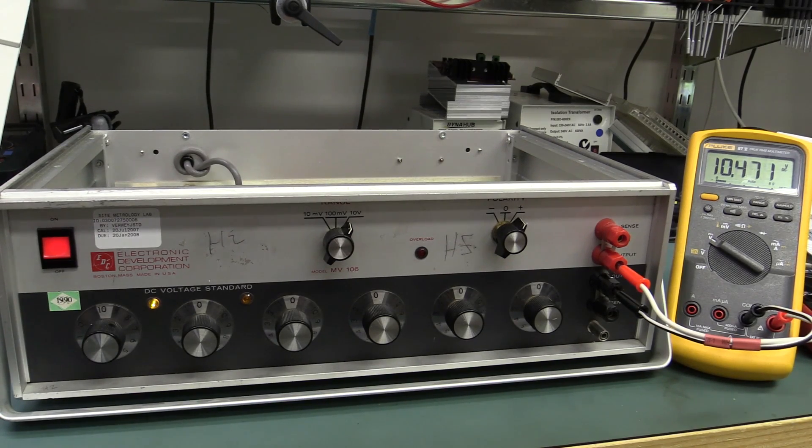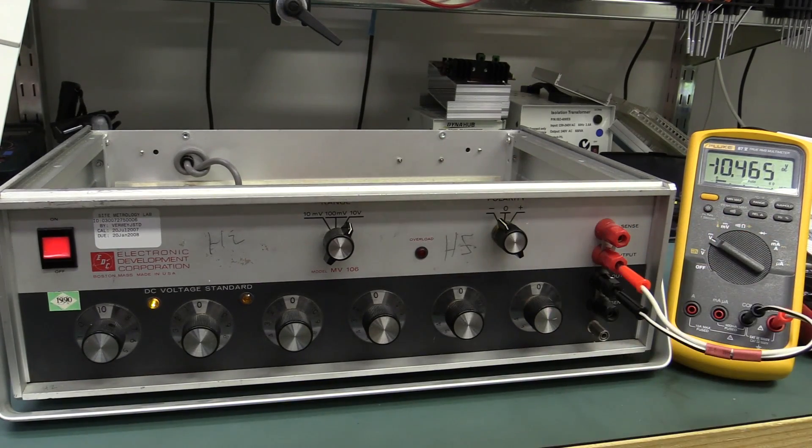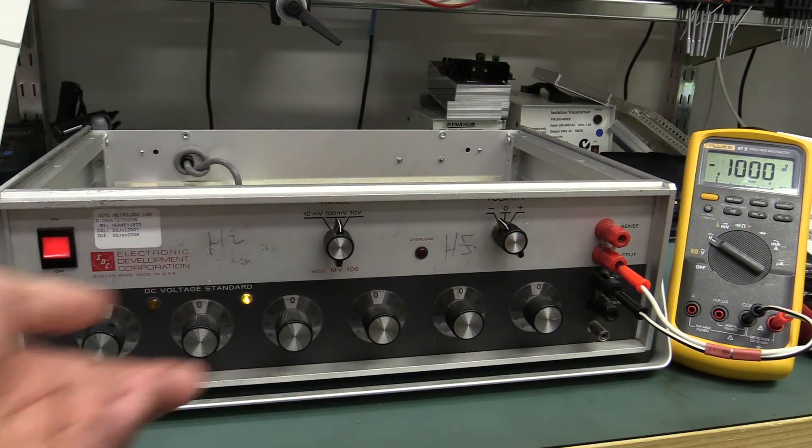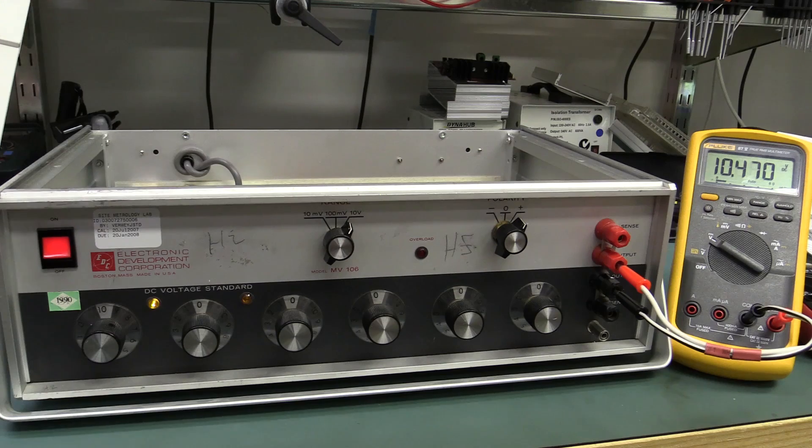But those were the symptoms. And it's not a dicky connection or anything like that. I turn it negative, and we get the negative. It works fine on the 100 millivolt range. So I thought somehow I've blown maybe the output of an op amp or something in the feedback loop or something like that. Even though the remote possibility what it was.